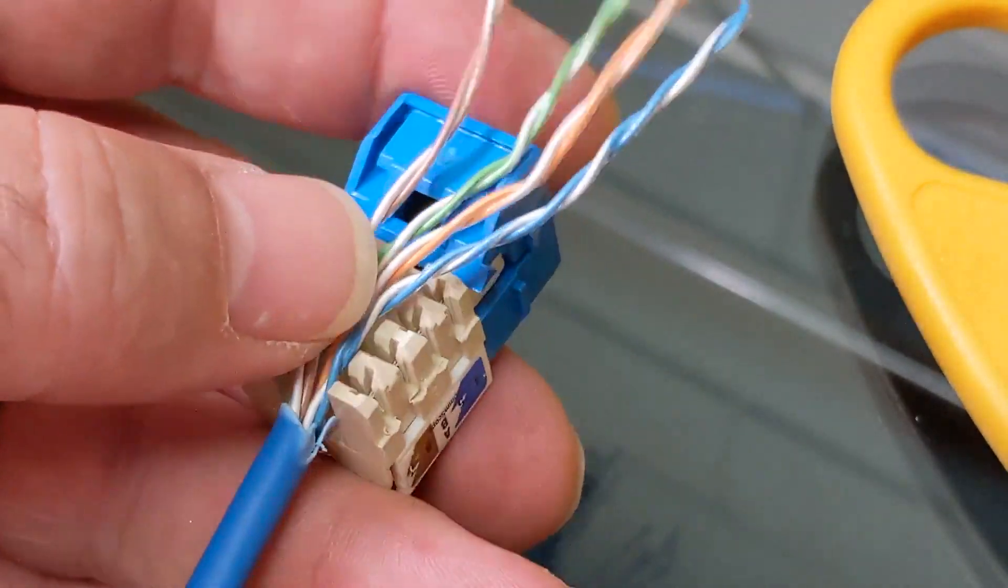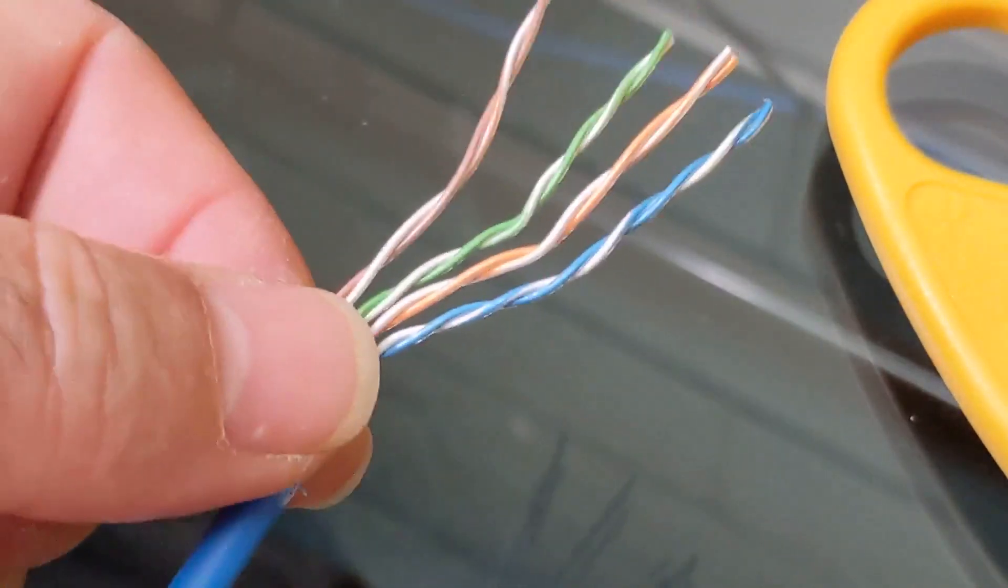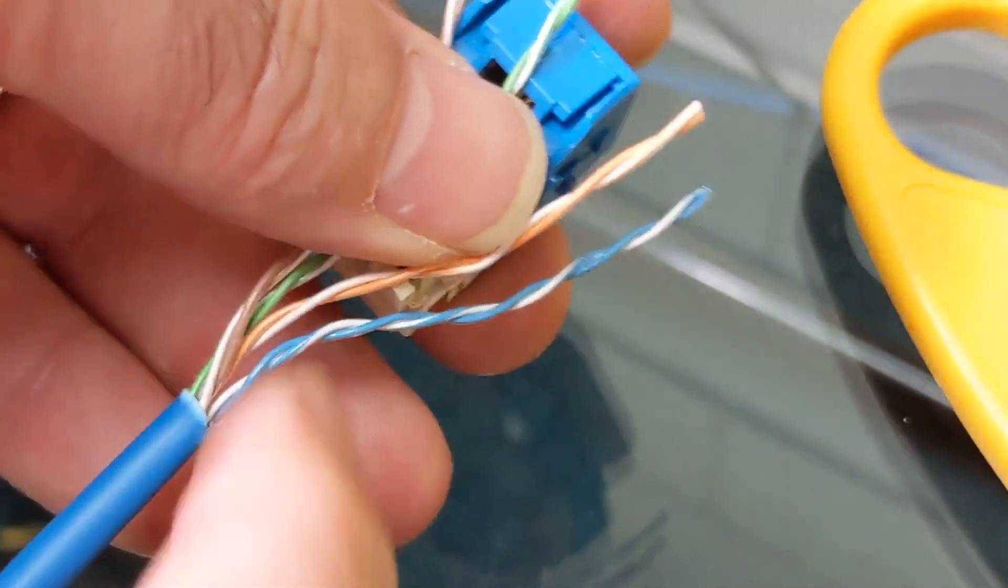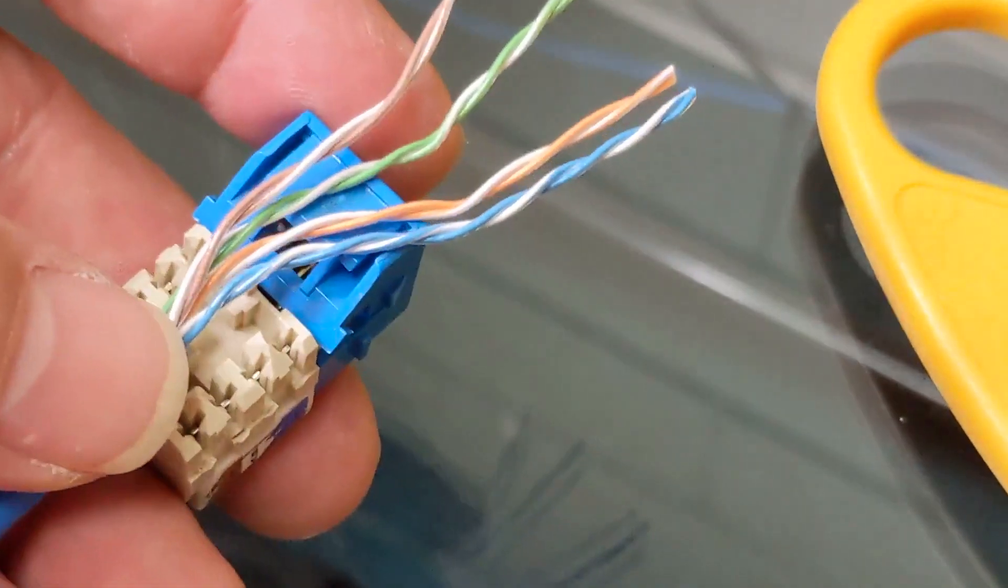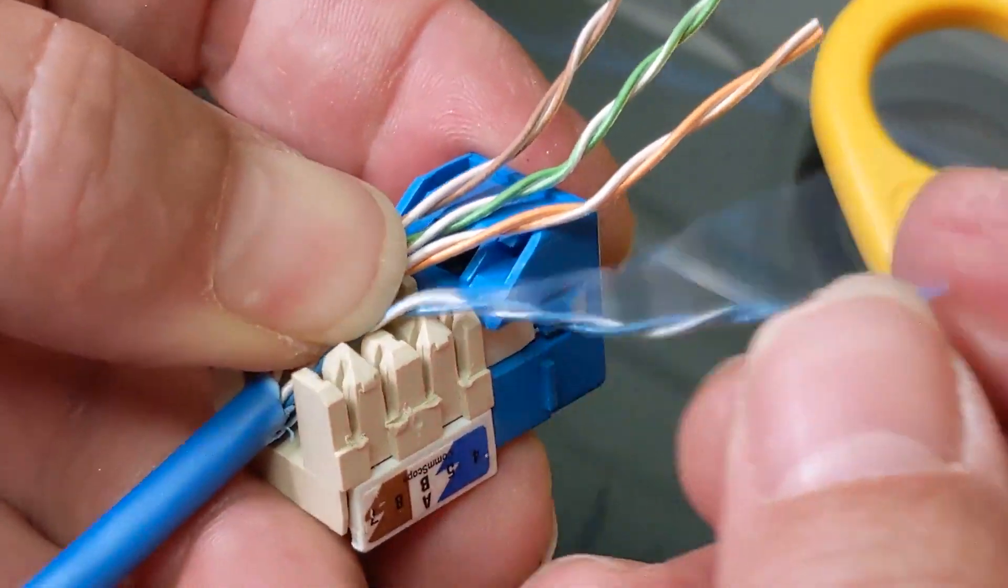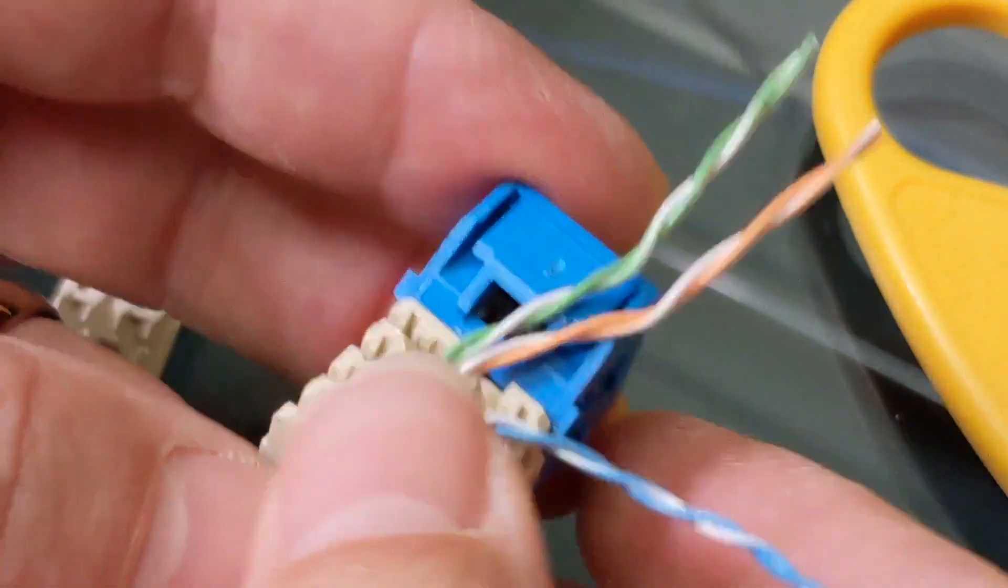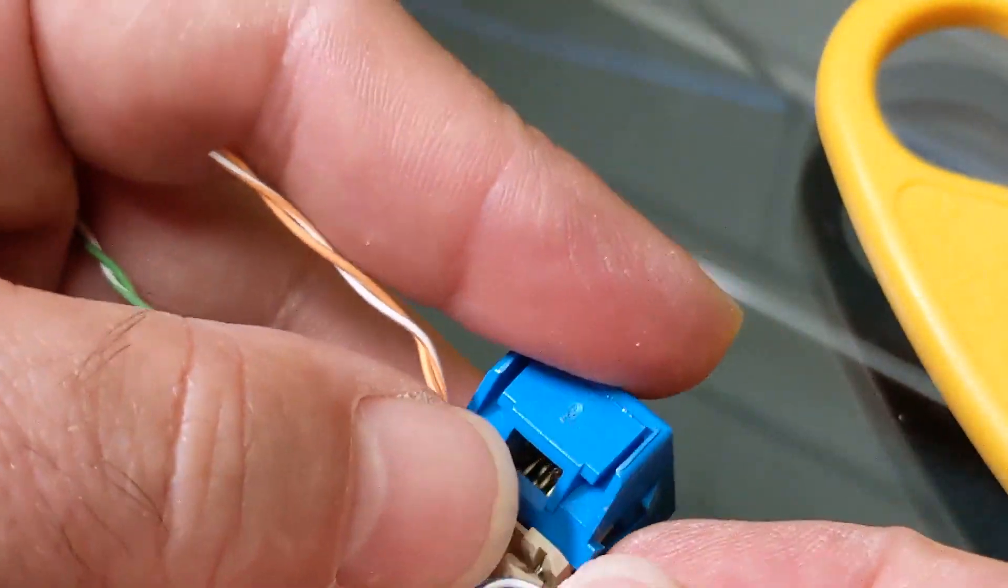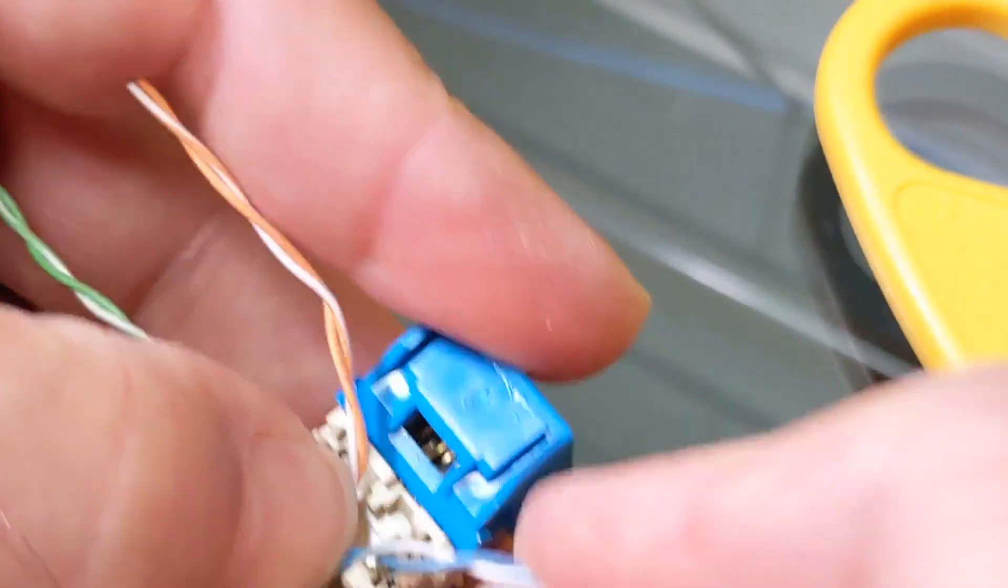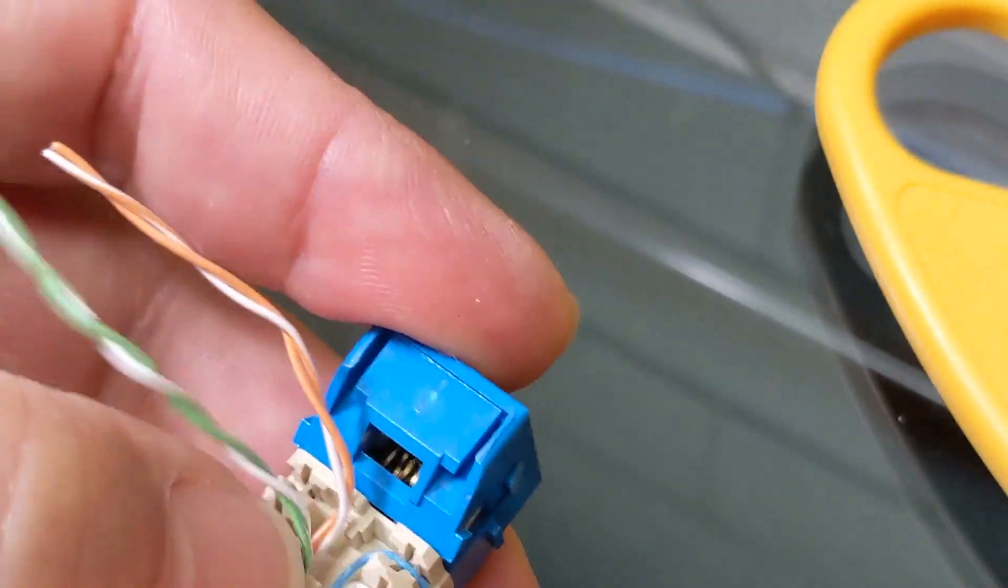While I do that, ideally I want to leave as much twist in the wire as I can. Because if I undo all the twist, and if I make a big long lead of exposed wire with untwisted, it makes it susceptible to noise. You want the least amount of untwist and exposed wire as possible. So let me take and put these into place. It helps if you fan these out in advance a little bit. I'll fast forward the camera, and then you can see what it looks like when it's all done.